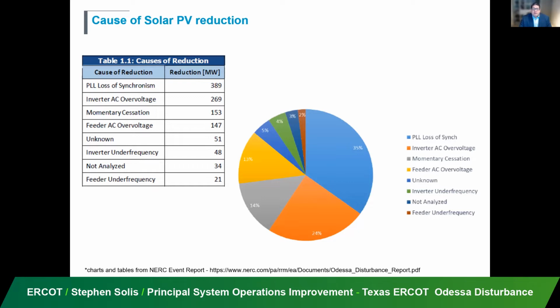We lost that generation. We also had some momentary cessation, where units tripped off or ceased generating megawatts for a few seconds and then came back about a minute later. And we also had some under frequency trips or reductions in megawatts, really faulty. Frequency didn't get that low, but their measurements caused them some issues.